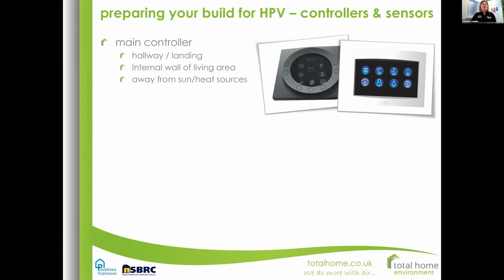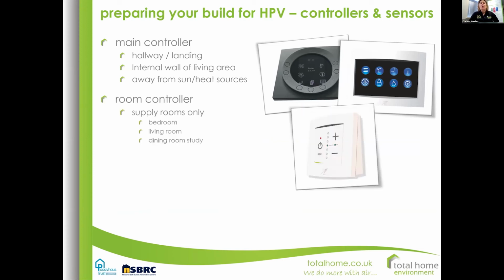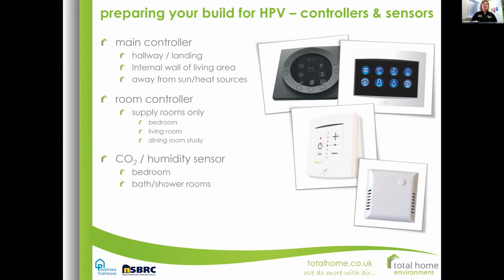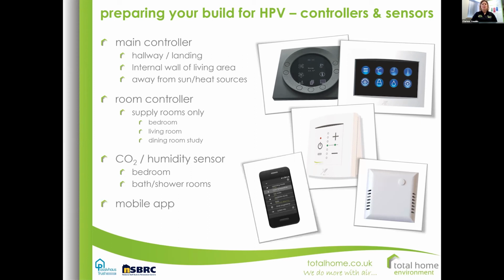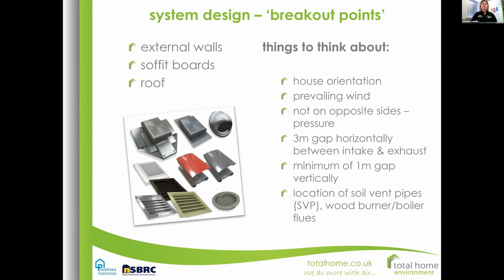Controllers and sensors and things like that: the main controller would always be in a common area away from sun or heat source, because obviously it's got sensors in it. And then if you have any individual heated ceiling terminals or radiant panels, then you would have a room controller as well. And of course there would be the carbon dioxide/humidity sensor, perhaps in bathrooms and living rooms. And you've got the mobile app as well.